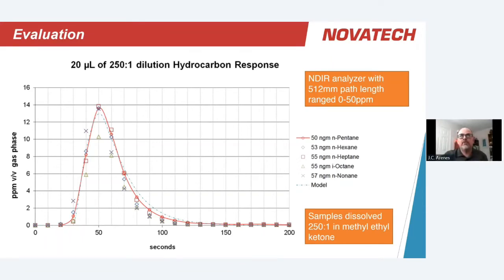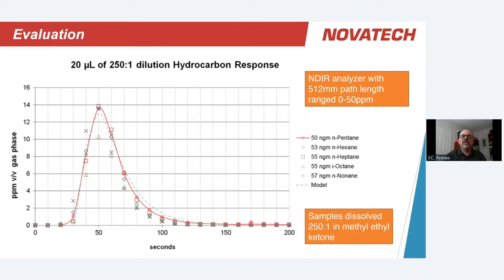These were 20-microliter dilutions at 250:1 ratios of hydrocarbons. We tested with pentane all the way up to nonane — C5 to C9 — measuring with an NDIR analyzer ranged 0 to 50 parts per million. We got excellent response, and all hydrocarbons followed a similar response pattern more or less in line with our modeling predictions. These first tests were very encouraging, with some fine-tuning and further testing still required to establish true performance limits.